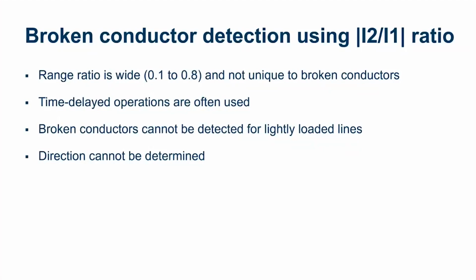The last thing here is we're not going to be able to determine the direction very well. If you have a broken conductor on a certain line, you want to isolate that line alone. If you've got a loop system with lines in front and behind you, you don't want to trip those either. So determining where the actual broken conductor is can be difficult using this method. Also, if we've got two broken conductors, you'll see that I2 is going to equal I1, so that ratio is going to be equal to 1, and we're not going to be able to detect that condition either.